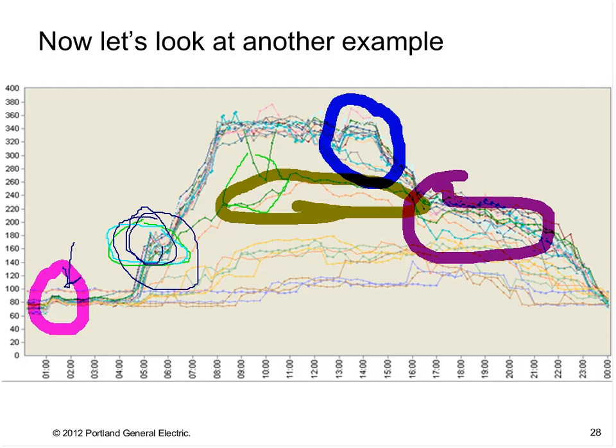All right, the next one over here to the left. Yes, I think these inconsistent startup times would definitely make me wonder what's going on. The forest green circle in the middle, this one here, that is a great one. That is actually a teacher in-service day, but you're wondering, okay, it's good we know that now, but why is there such a large load shape when it's not flat, but it's not a full day's use? That is a teacher in-service day.